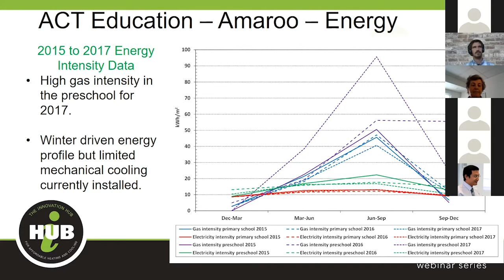In the past little while we've installed a very comprehensive monitoring system across all the schools, common between Amaroo and Fadden next door. We've installed a weather station at each school with remote communication, energy consumption monitoring using Wattwatchers devices, and an IoT LoRa temperature monitoring system that also includes CO2, occupancy, and lux levels. We're also monitoring gas consumption, and we connect into the BMS system, although that has limited usefulness given it's not the most reliable system.